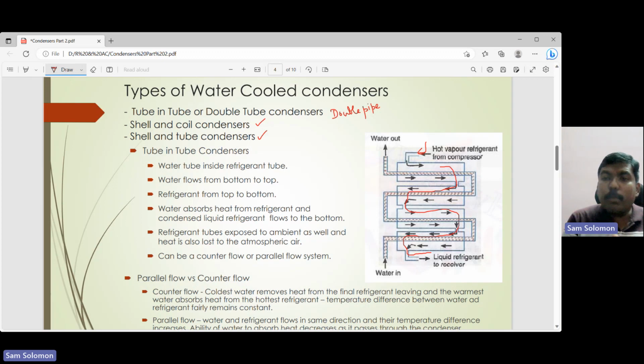So what is done here is the cold water is passed alongside the refrigerant that is flowing through these tubes. The tube that passes the refrigerant is the outside one, and the tube that is carrying the water is placed inside the tube carrying the refrigerant. Okay, so that is a tube in tube. The outer tube carries refrigerant, the inner tube carries water. So the water is capable of removing heat from the refrigerant as it goes out.